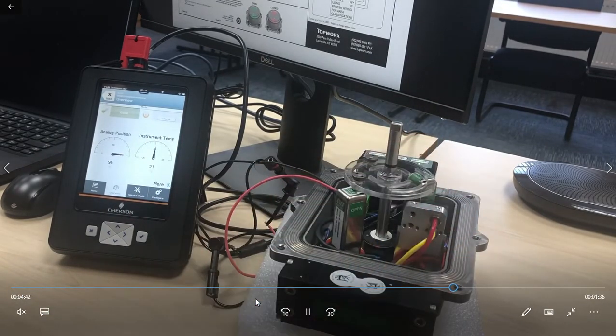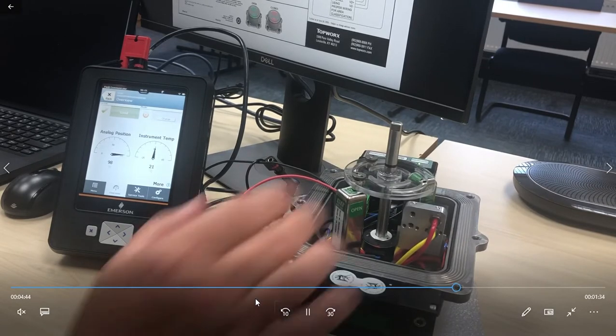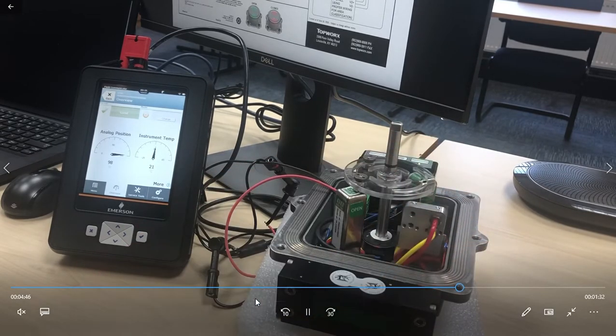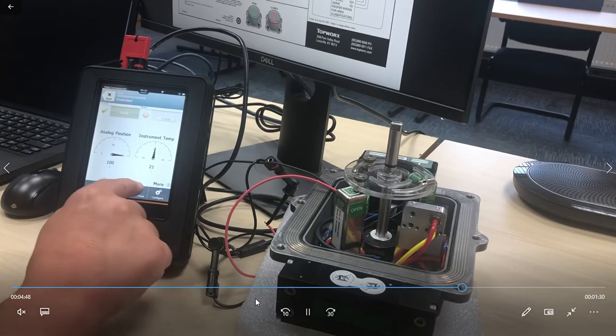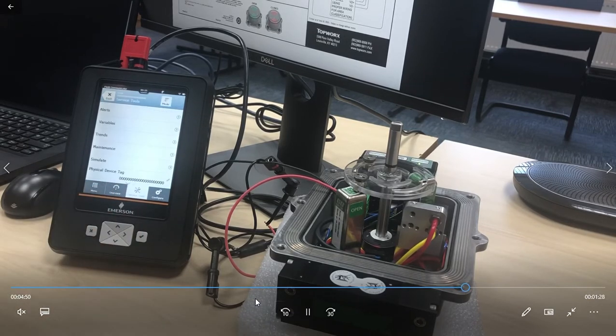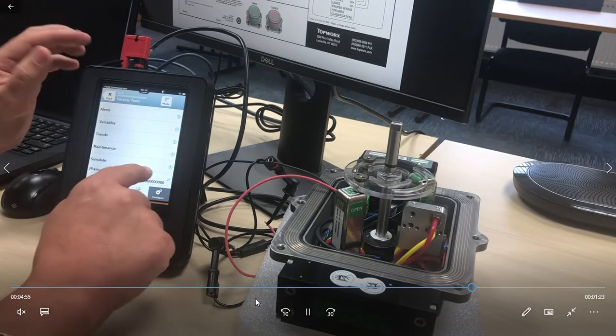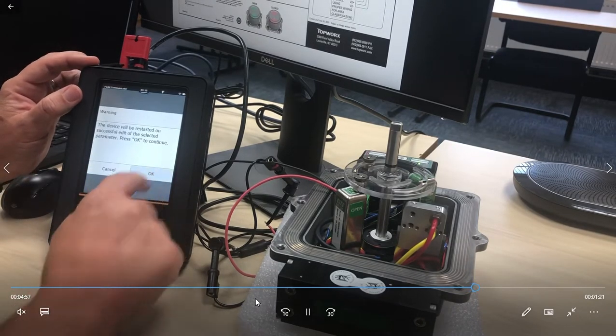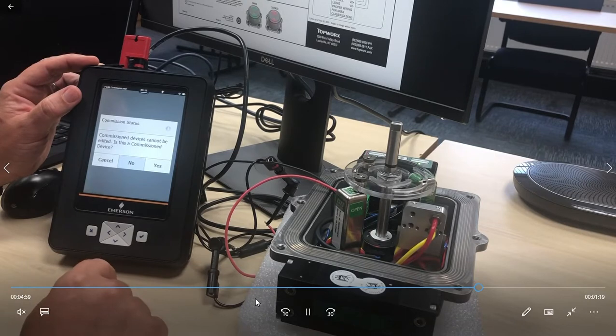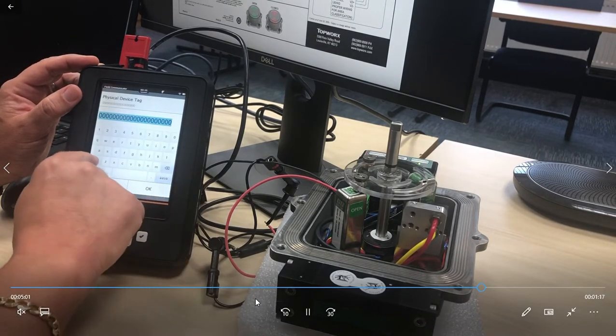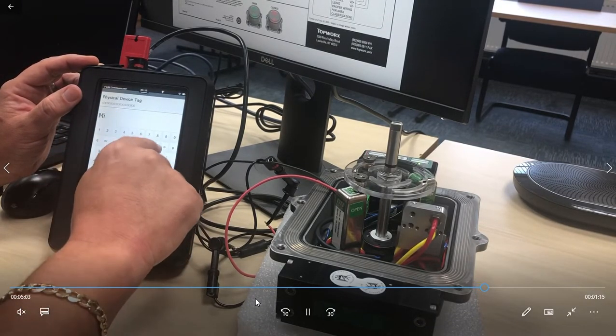So as you can see there, it's registering the analog position in terms of a percentage. So I've just moved it a little bit there to ensure it's 100%. And now we're just going to have a look at some of the other variables that you're likely to change, especially on commissioning. A lot of devices now have a tag number, and these are sometimes a stainless steel tag on the outside of the device.